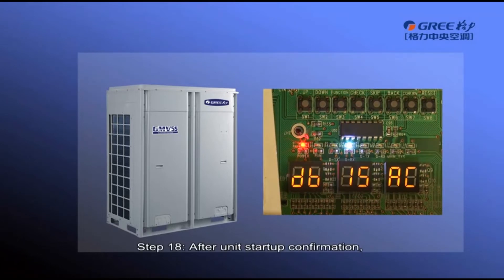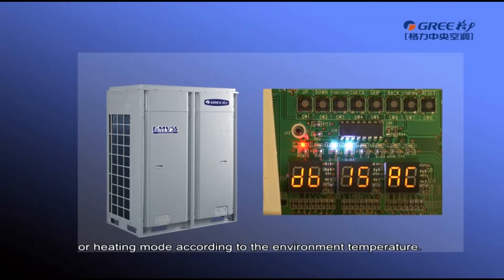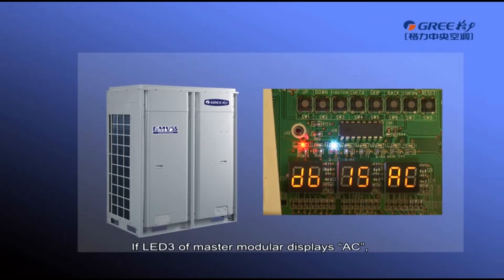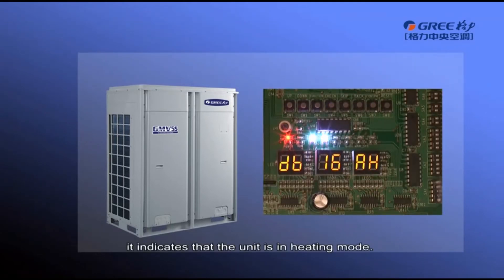Step 18. After unit startup confirmation, the system automatically selects the cooling or heating mode according to the environment temperature. If LED3 of the master unit displays AC, it indicates that the unit is in cooling mode. If LED3 of the master module displays AH, it indicates that the unit is in heating mode.